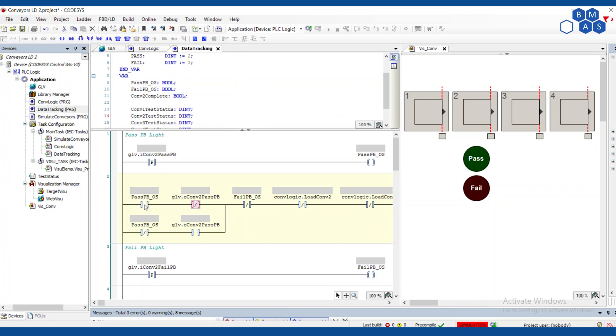So during that one scan, when the one-shot is true, we're going to make that light whatever the light is not. So if the light is off, we're going to turn it on. If the light is on, we're going to turn it off. And then whenever we're not in that one scan, we're not trying to toggle it. That's this rung here, we're not trying to toggle, then whatever that light is, keep it that same way. So this is the toggle condition. Often we see this as like the on condition. In this case, it's the toggle condition. And then this is the latch condition, holds itself as it is.